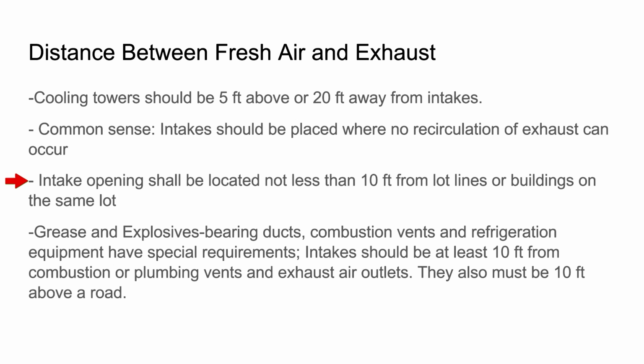The 10-foot rule, essentially, everybody probably runs off of it. There are a little bit more in-depth things, but essentially you don't want to be within 10 feet from an exhaust and an intake. Intake openings should not be less than 10 feet from lot lines or buildings on the same lot. So you can't vent out the side of the building right into your neighbor's building. You can't vent out the side of the building at head height right by a sidewalk or by a road. And so it's always 10 feet for whatever reason on all of them. So you're pretty much just looking at, if I'm exhausting something, is it 10 feet from anything? If my intake is there, is it 10 feet away from any exhaust or anything that's going to be bad that you don't want to be pulling back into the unit?